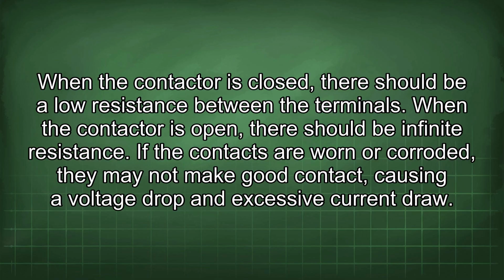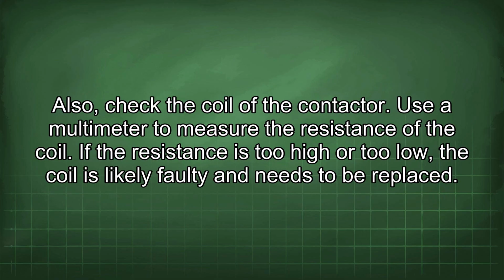If the contacts are worn or corroded, they may not make good contact, causing a voltage drop and excessive current draw. Also, check the coil of the contactor. Use a multimeter to measure the resistance of the coil. If the resistance is too high or too low, the coil is likely faulty and needs to be replaced.